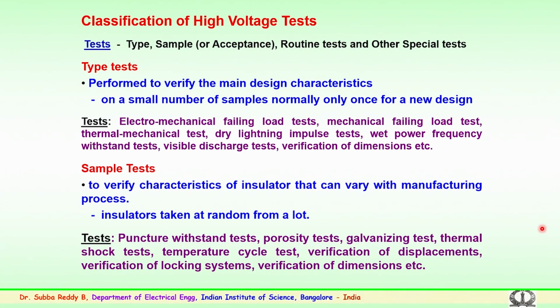The third is routine tests, which are normally conducted on each and every component in the industry, and some other special tests as the voltage levels go up above EHV and UHV. Apart from type, sample and routine tests, a few special tests have also been introduced to verify the design of the insulation when used for ultra high voltage or extra high voltage transmission systems. So, the type tests are normally performed to verify the main design characteristics on a small number of samples, and normally once for a new design.